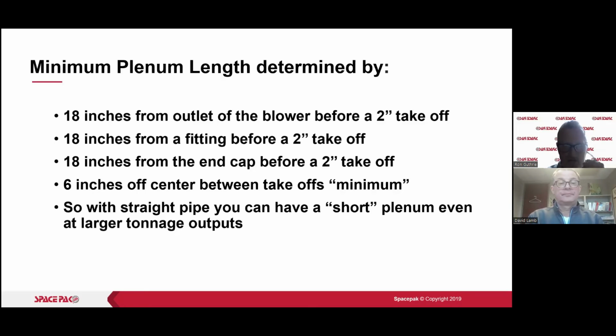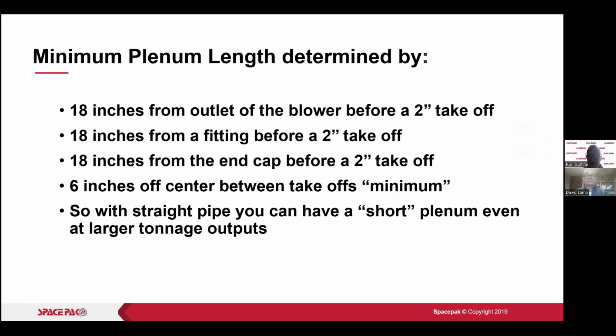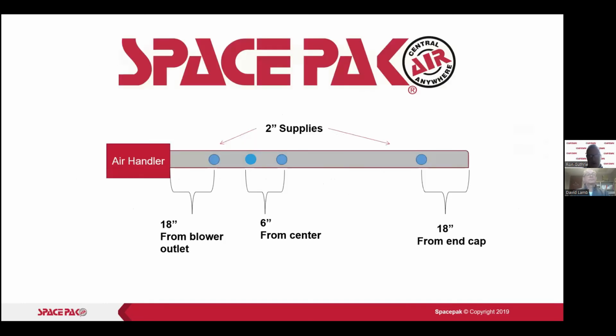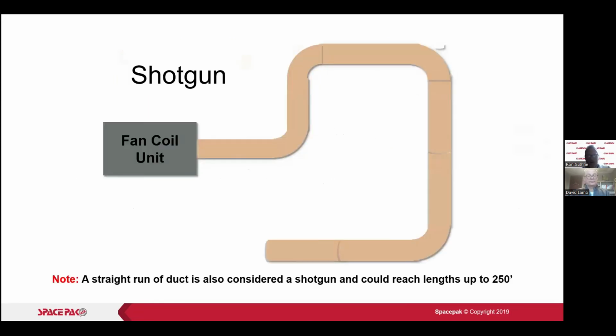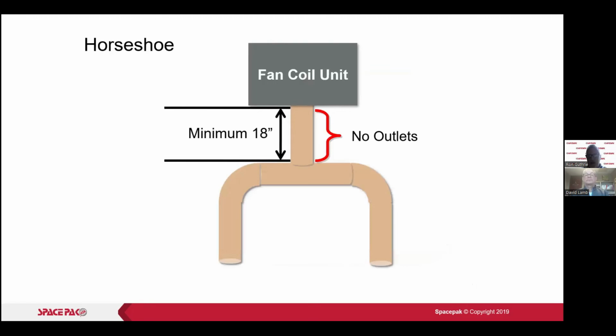So that's just showing the minimum right there. With straight pipe, you can have a short plenum, even at larger tonnage outputs, because we don't have all of the fitting clearances that we have just above. All right, so 18 inches from the blower before an outlet, or before a fitting, 18 inches up from an end cap. All right, shotgun, straight run of duct. Straight run without all of these elbows in there is also considered a shotgun. Straight on down. Okay, no outlets on that 18 inches, and it is 18 inches before the fitting, a T or an elbow.